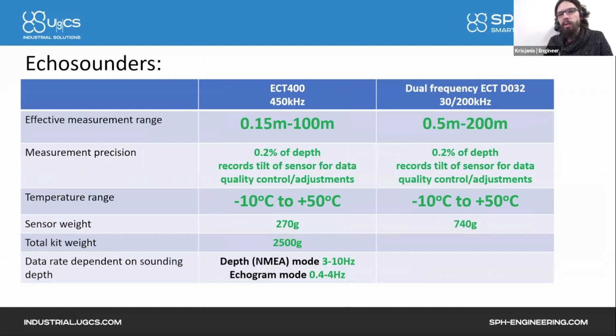Okay, we are currently offering two echo sounders. One is the ECT 400 single frequency scanner, and the other is ECT D032 dual frequency scanner. The effective measurement range for the ECT 400 is from 15 centimeters to 100 meters. And for the dual frequency echo sounder, it is from 0.5 meter to 200 meters.